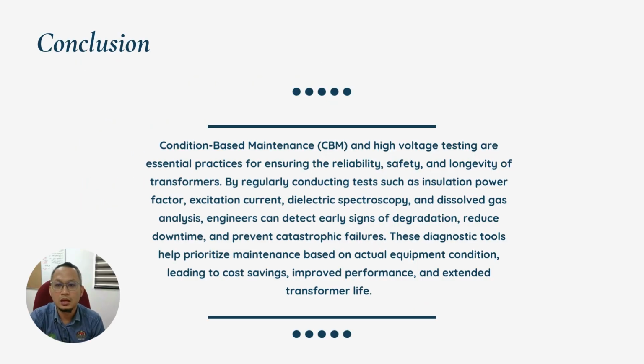In conclusion, condition-based maintenance, CBM, and high voltage testing are essential for maintaining the reliability, safety, and longevity of transformers. By regularly conducting tests like the insulation power factor test, excitation current test, dielectric spectroscopy, and dissolved gas analysis, we can detect early signs of degradation, prioritize maintenance, and prevent catastrophic failures. This practice not only reduces downtime but also helps extend transformers' life and improve overall performance.